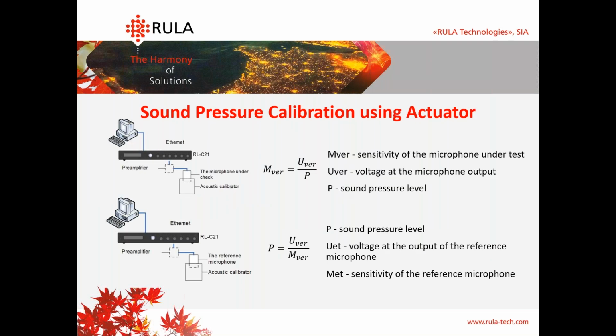Also, when you use a sound calibrator and actuator, it becomes more complicated. On the first step, you need to place the microphone under check into the acoustic calibrator. In that case, you find the sensitivity of the microphone under test. Also, if you don't have a reference acoustic calibrator, you need to find the sound pressure level using the reference microphone. Here you see the formulas and the connection scheme. I think you will get this in the follow-up.